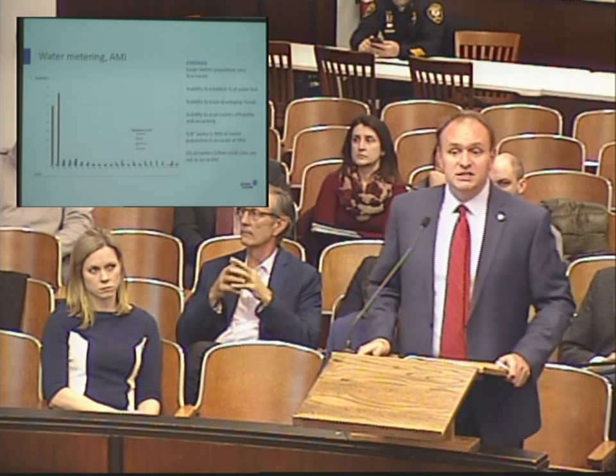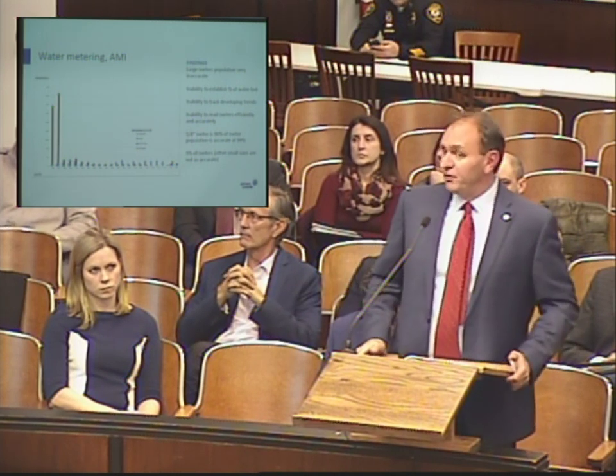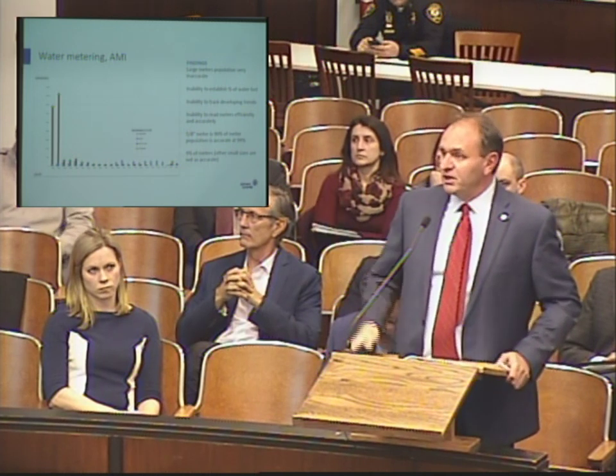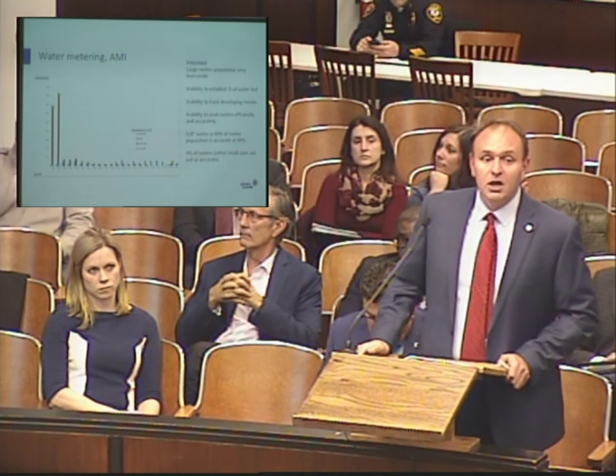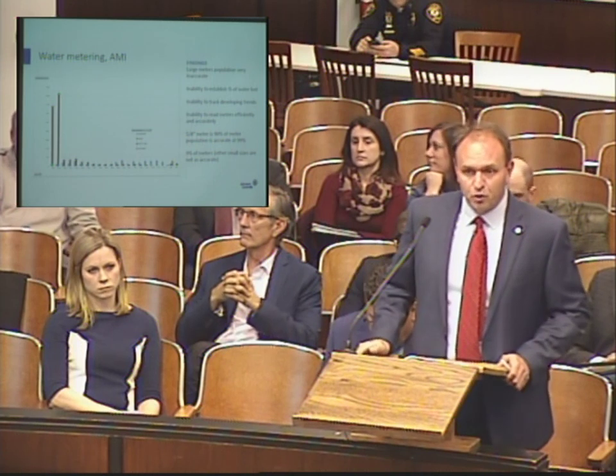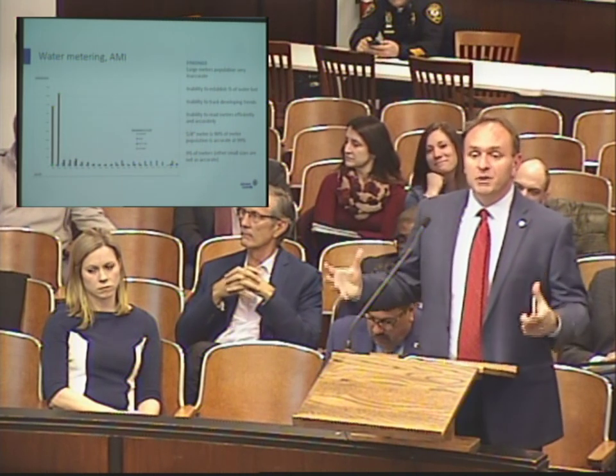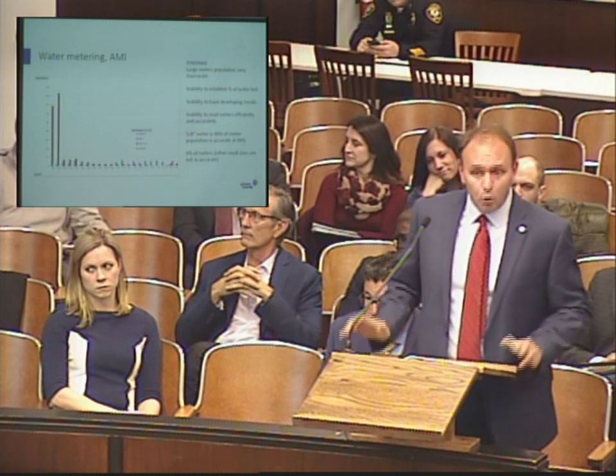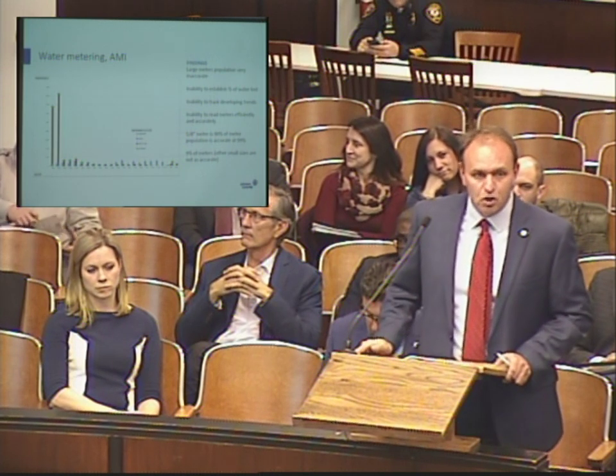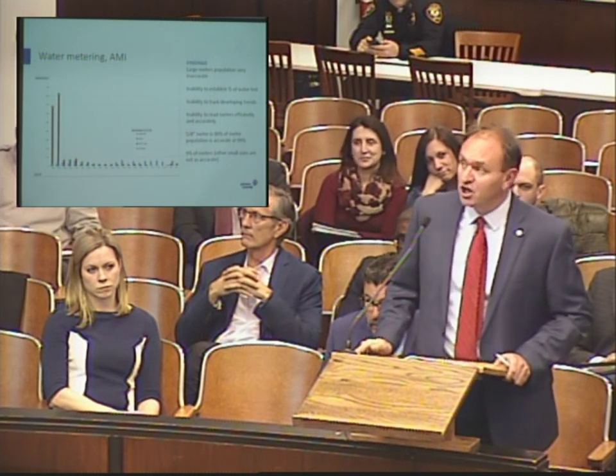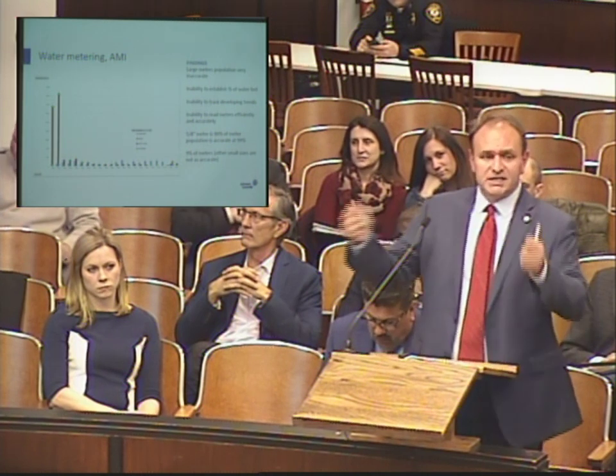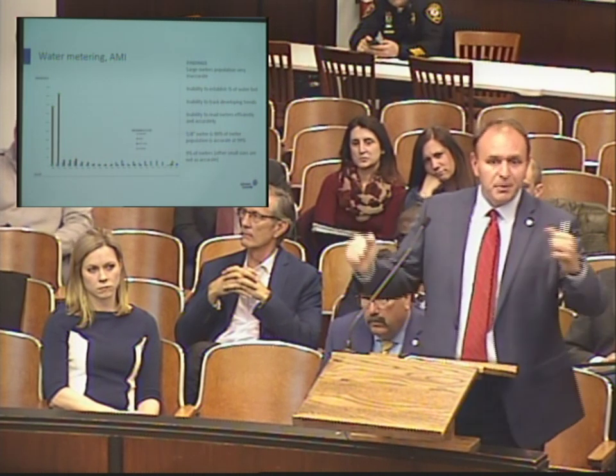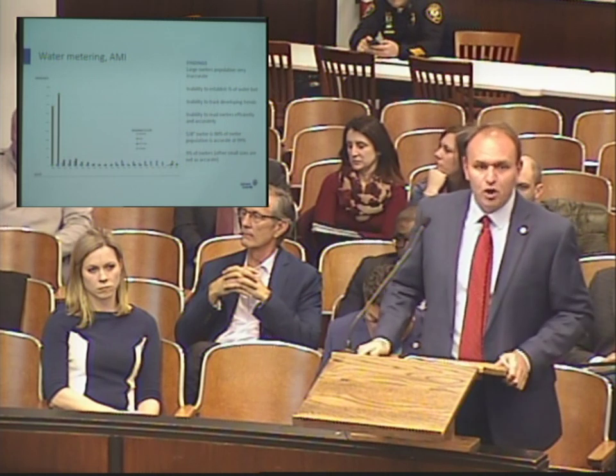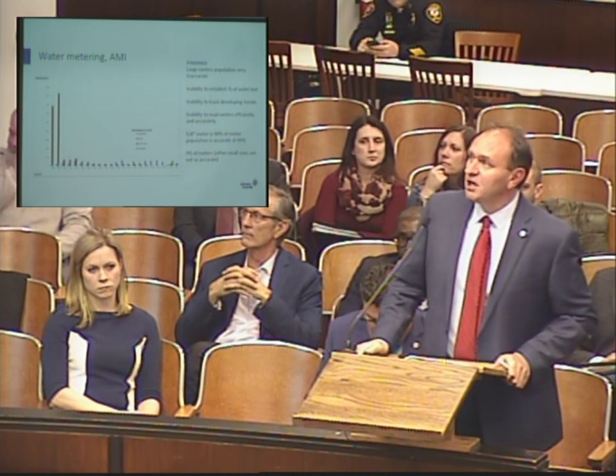What we found is that your large meters are very inaccurate. 30, 40 years ago, when they were installed, there were only certain choices of water meters, and your meters are quite inaccurate. So we are strongly recommending replacing all of the large water meters. And it's not just replacing meter for meter, it's also repiping and adjusting. There's a lot of work involved in these 100 meters.